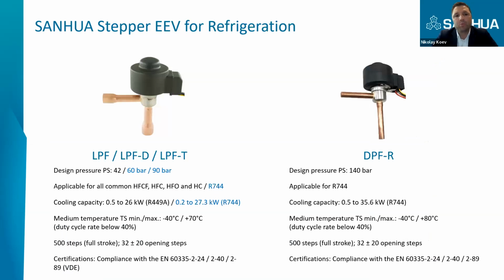So we developed electronic expansion valves specifically for commercial refrigeration applications. Our model LPF has several modifications with different design pressures: 42 bar, 60 bar, and 90 bar. LPF is applicable with standard refrigerants, and LPF D and LPF T with CO2. What is specific for this valve?